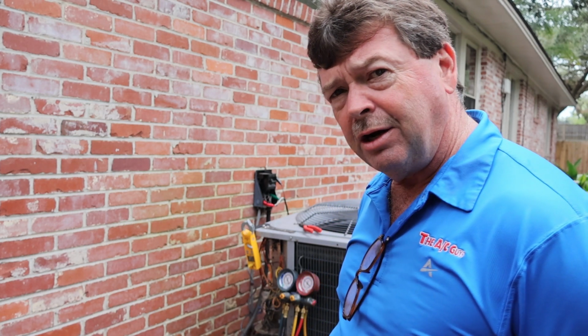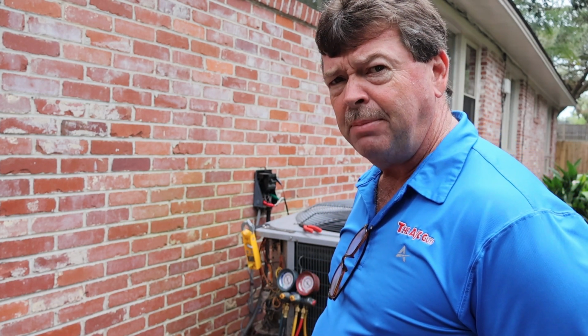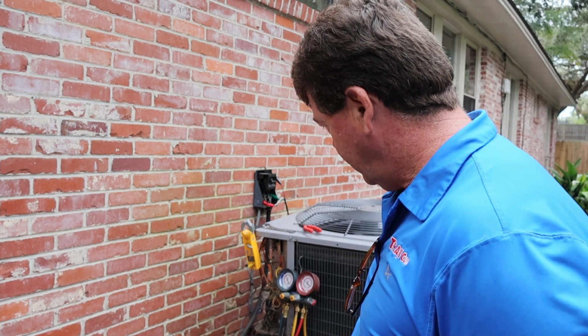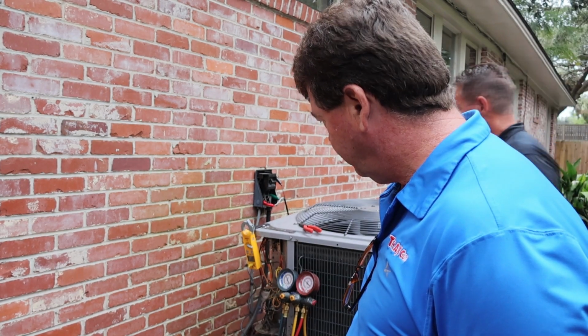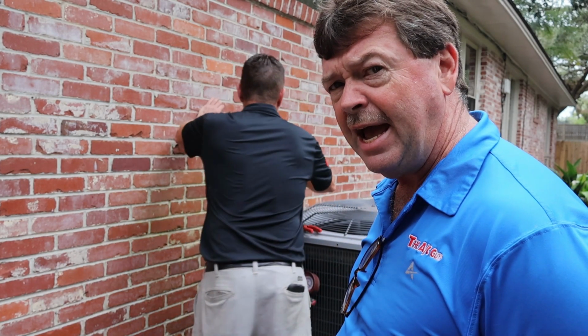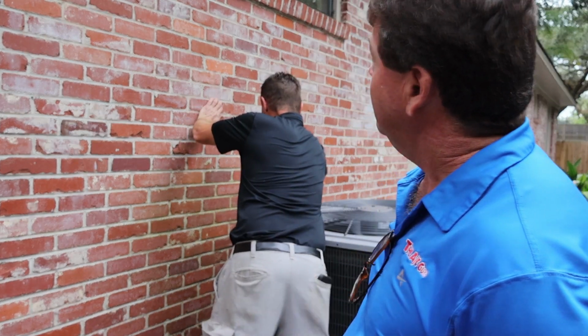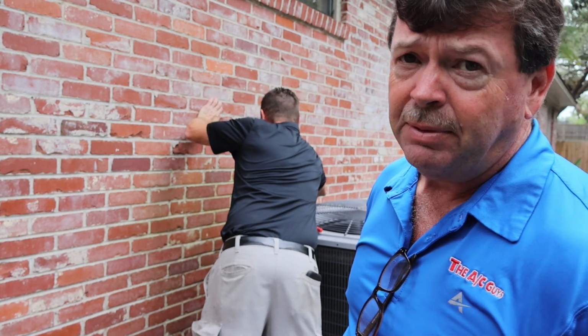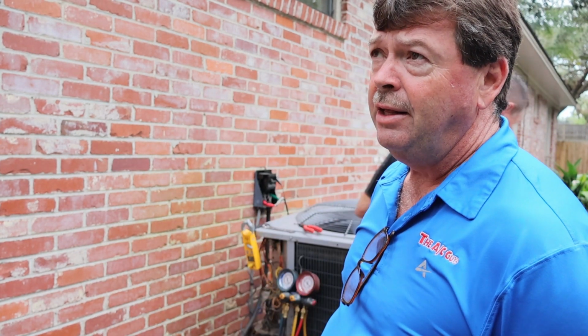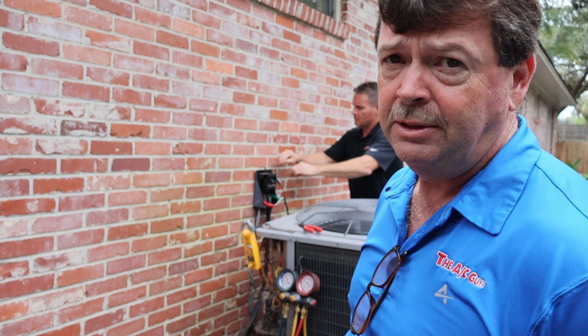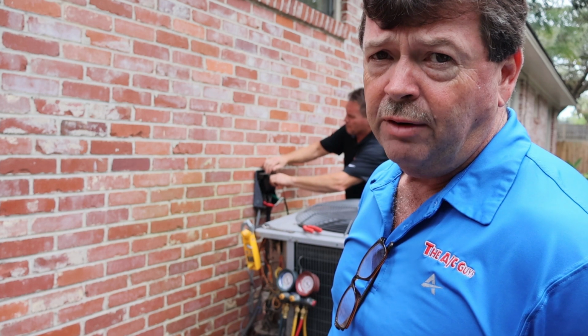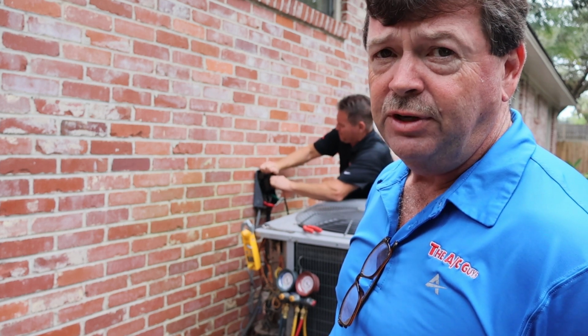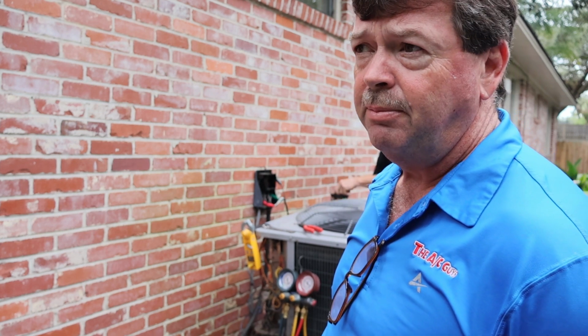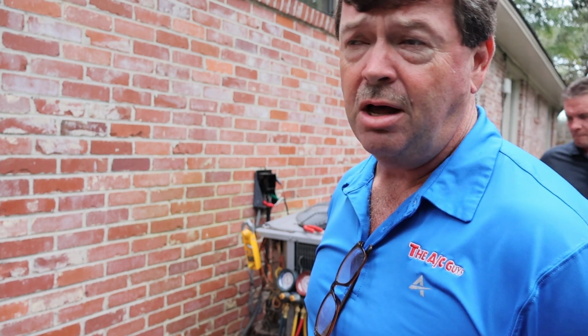So we're going to clean it now and clean the leaves out, address that part of the maintenance, and then we'll move to making sure the drain as it exits the house. Make sure that if it is in an attic, in this application it's not, that it's got a secondary drain on it, that the drain comes out the soffit, and make the homeowner aware of where it's at if they don't already know, because if you get water dripping from the soffit, typically the problem is your safety pan is full of water and you got a primary drain line that's clogged.